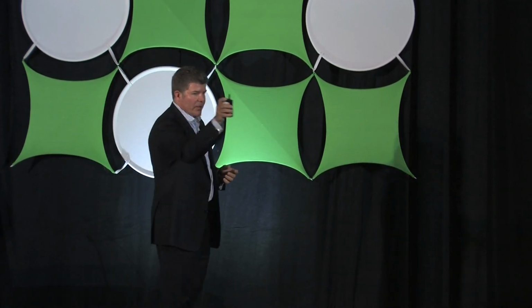What you're looking at is inside the row of one of our in-row cooling units, looking right down the middle of the row. All those little circles on both sides of the row, those are the server fans. Inside, it's a hot aisle containment.